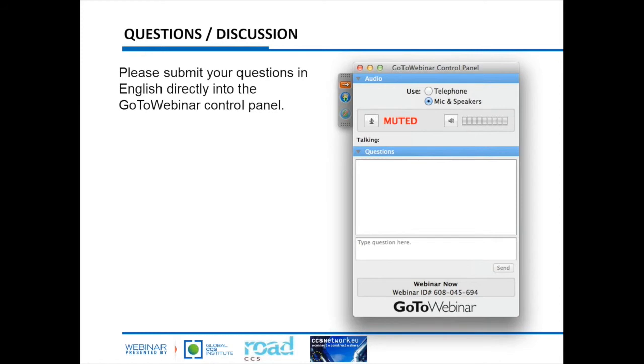Okay, thank you. With regard to the cooling seawater intake, has this been designed with additional capacity in terms of future expansion for the capture, for further capture units retrofitted to the plant, and have you factored that into your associated permits for seawater intake? No, the simple answer is no on all counts. The power plant was permitted without carbon capture, although it is carbon capture ready. And if we do full-scale carbon capture, we will have to have a new cooling water intake.